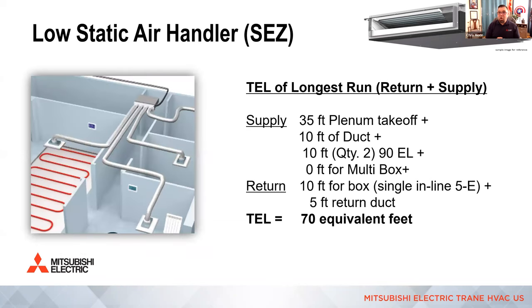All right, so moving on to the bottom side. Total equivalent length of the longest duct run. And this is typically found on the back side of a lot of duct calculators, right? So there's a lot of fitting values. If you ever work with the actual Manual D, it's probably 300 pages and at least two-thirds of it is just pictures of fittings in order to explain what the equivalent length value is. Now, equivalent length value is based on pressure drop for that particular fitting. So the lower the equivalent length value, that means the easier it is for the air to move through that fitting.